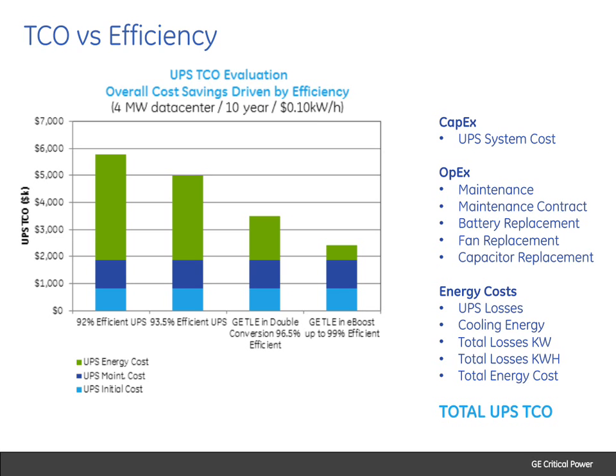The first bar shows a UPS with a 92% efficiency level. If you look, there are 3 sub-bars: the cost of the equipment, the maintenance cost, and the energy consumption cost. By far, the cost of energy in that scenario is much greater than the cost of the equipment or the maintenance costs.